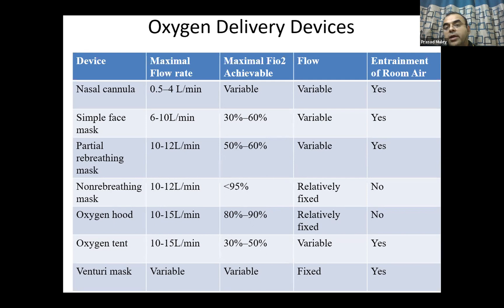Nasal prongs are a device that ends in two short tapered tubes about 1 centimeter in length, designed to lie just beneath the nostrils. They are also called nasal cannulae. Standard flow rate, as we already discussed, is 0.5 to 1 liter per minute for neonates, 1 to 2 liters for infants, and 1 to 4 liters for older children. It is somewhat arbitrary, and we always keep adjusting plus minus depending upon the SpO2 level in our patient. It is not hard and fast, but it is the recommended range in which we give oxygen through cannulas in neonates, infants, and older children.